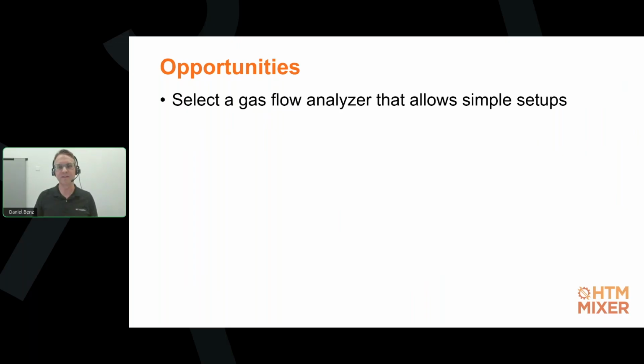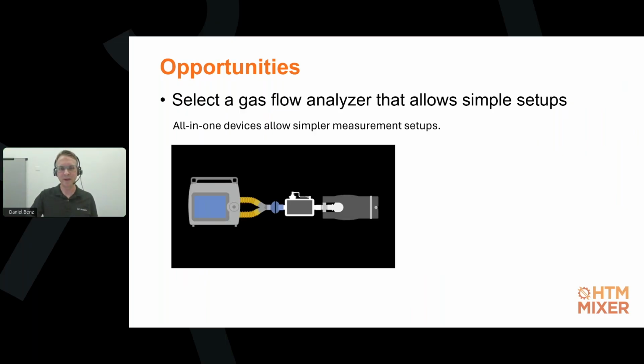The opportunity for test equipment manufacturers is to design the device in a way that it allows simple setups. So when you choose a gas flow analyzer, we always recommend that you select one that is designed with a focus on allowing simple measurement setups. Such devices are usually called all-in-one devices, where all the relevant parameters are measured inside a single flow channel. So this is an example of a gas flow analyzer in the schematics here. This is the ventilator, and all-in-one devices just measure everything inside the one flow channel. So with that, the setup is usually very simple.